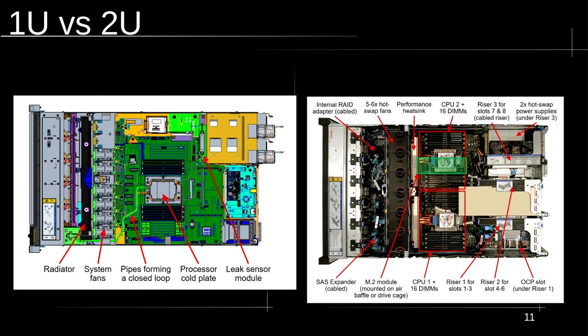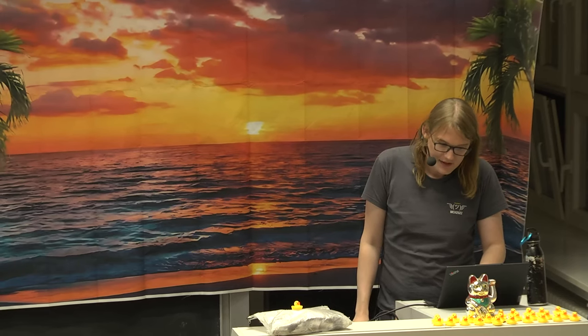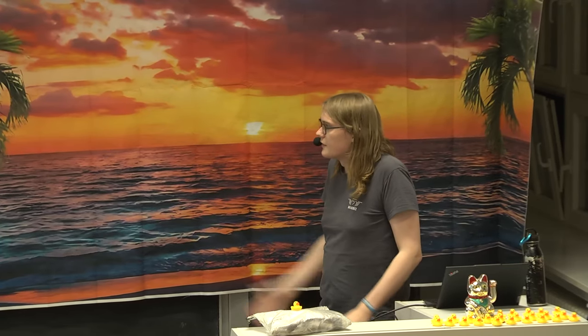Let's look at some normal servers. There's been a long discussion about 1U pizza-box format versus 2U. You can fit twice as many 1U servers in a rack, but given CPUs now do 400 watts instead of 200 watts, most manufacturers now have to go to liquid cooling to fit it in 1U. The 1U server on the left has integrated water cooling — a closed loop — just to dissipate 400 watts of heat, adding complexity and cost. A more traditional 2U server has much bigger fans and can even fit two CPU sockets, using far less fan energy.